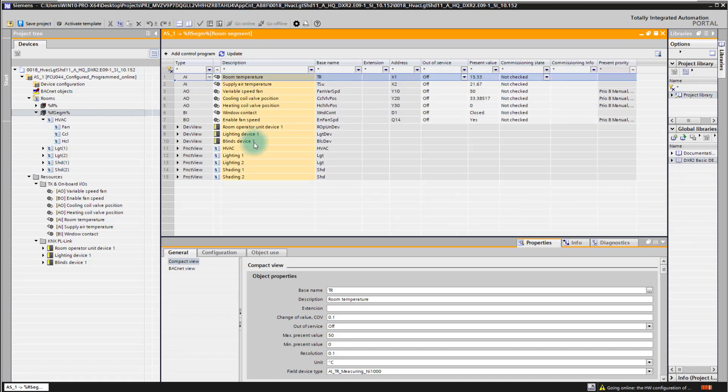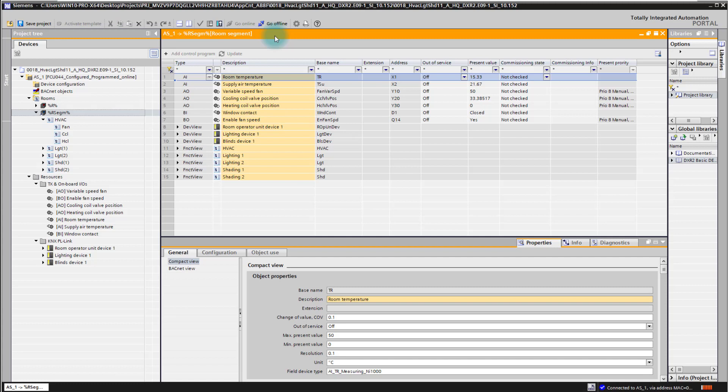Simply by pressing here the menu bar go online we are changing into online mode and connecting to the controller. You see here the orange indication at the top which says this data is now online on the controller, and you see also directly a change in the columns of the editor as we show now the most important online data of the objects and of the points in our room segment editor.